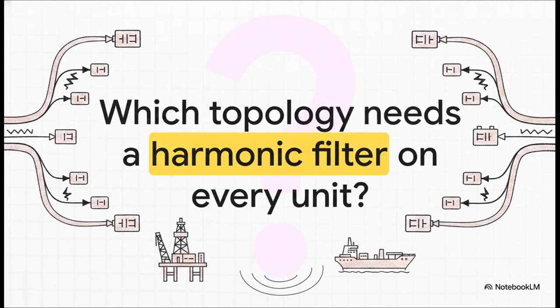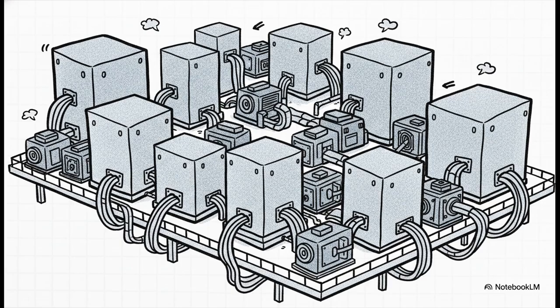bus. So, quick check to make sure we're tracking this flow. Based on how power is drawn, which topology forces you to place a harmonic filter on every individual drive unit? Yep, it's the single drive. Because every unit has its own isolated rectifier pulling straight from the main switchboard, you are forced to mitigate that distortion unit by unit. That means buying, wiring, and installing a mandatory harmonic filter for every single drive. And of course, that adds back more weight and gobbles up even more of that precious, precious real estate.